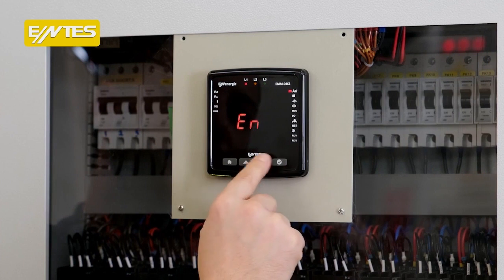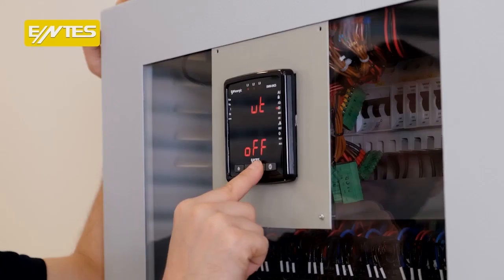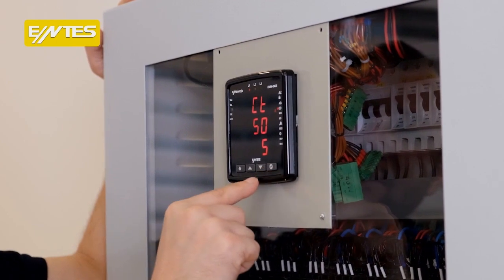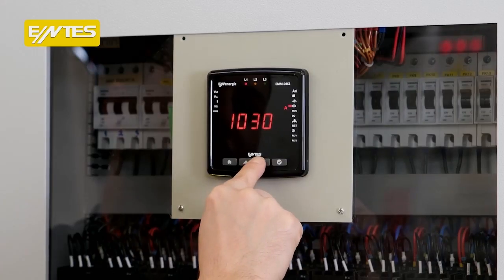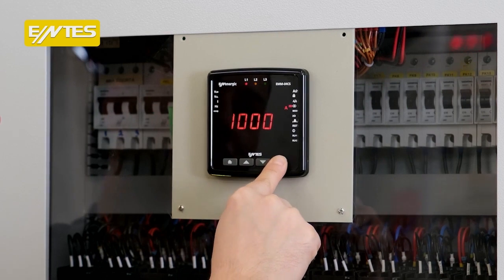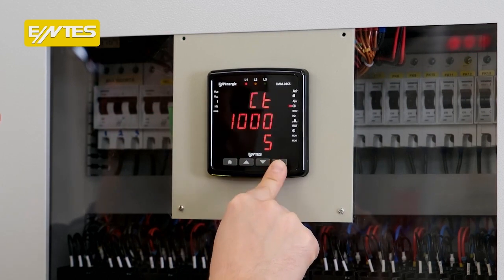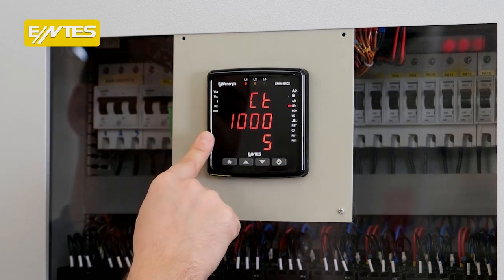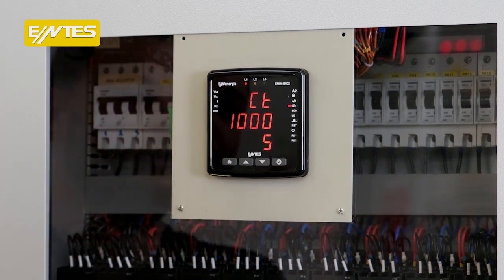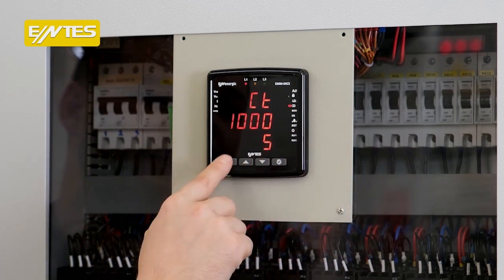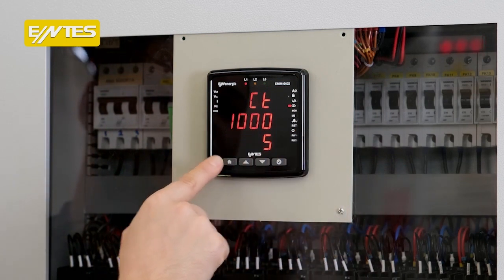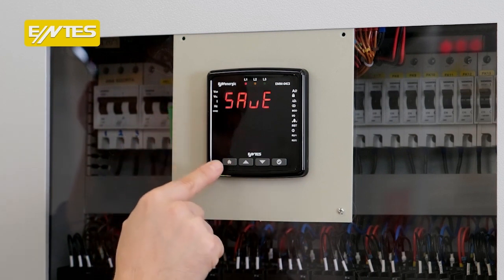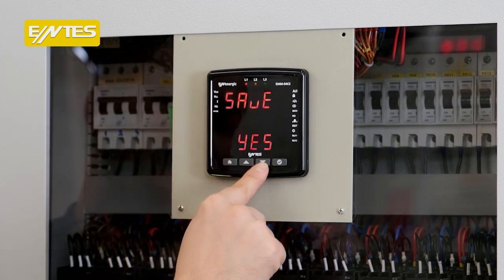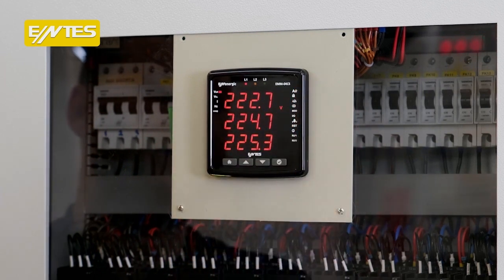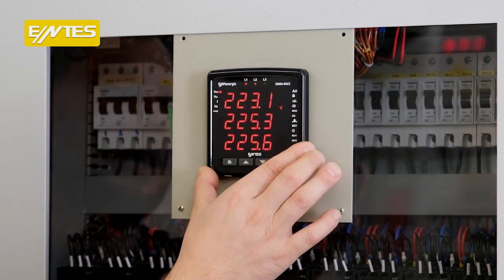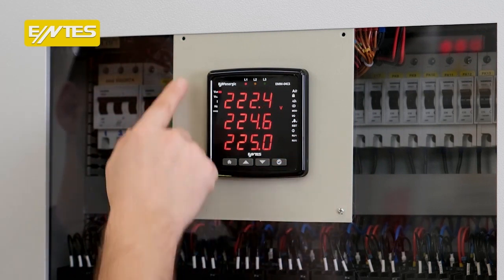I'm giving an example here. We can change our current transformer. I changed it from 1000 to 5. I accepted the secondary again as 5. Look, we set it to 50 to 5, but later I connected a 5 CT to 1K, so I made changes to the menu. This step is important. I made the change, I approved it. Now I leave with the home button. I pressed it once. Save came. When I turned no into yes, the device saved the most recent change I made to its memory. The installation and usage of the device is as follows.